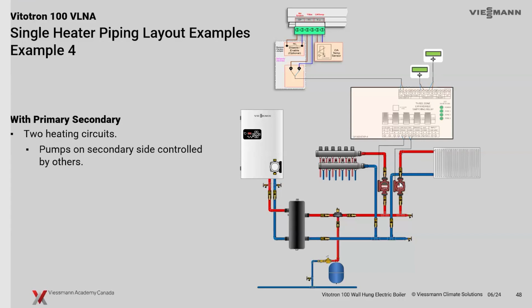And of course, you don't have to have balancing valves in this application. We're going to essentially allow the pumps to operate based on their pressure drops for their individual emitters here. Same thing, just a dry contact off of our little zone box back to our boiler. Boiler gets the call for heat, and whatever that set point is for that particular time of day and with the temperatures outside, that boiler is going to fire to that and stage based on what we're looking for.